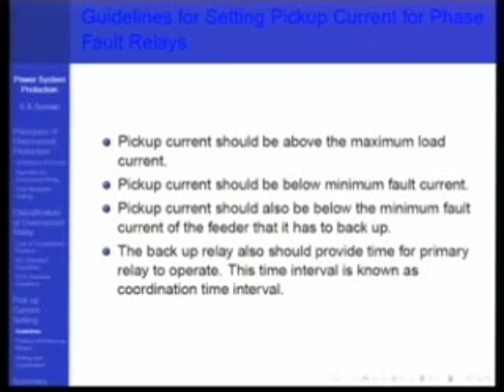And the backup relay also should provide time for the primary relay to operate. This time interval is known as coordination time interval. I have already mentioned it. So if you are not able to achieve it, I am not saying that because I have put up a slide you can achieve it. If you are not able to achieve it, then overcurrent protection is not the philosophy to be used. Then you may have to use, as I said, the standard mantra I would keep on saying, go for current differential. If you go for current differential, most of the problems will anyway go. But it has an additional cost, communication and so on.